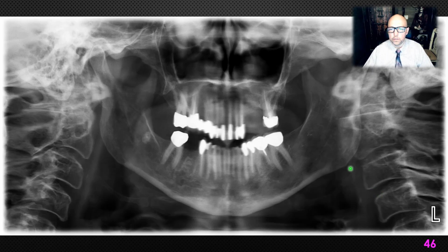This one, the positioning is what really stands out to me. What did we say about that from your panel lecture? Narrow teeth anteriorly, were they too far forward or too far back? I guess the amount of spine that shows in this case may be a hint as well. They were way too far forward. You get forward of the focal trough, and those teeth narrow.